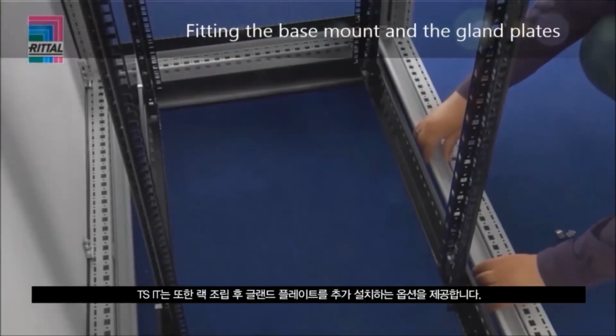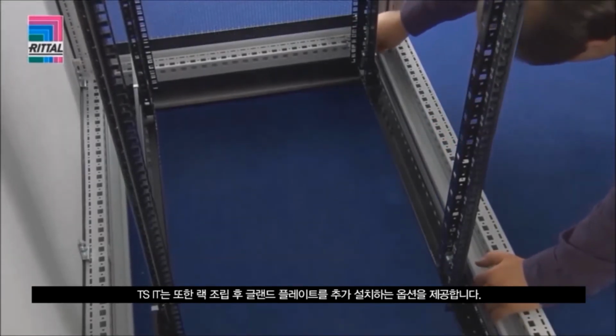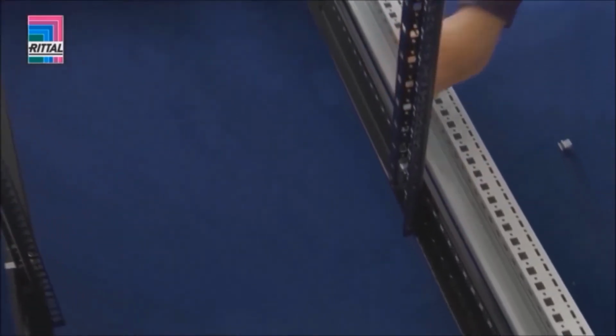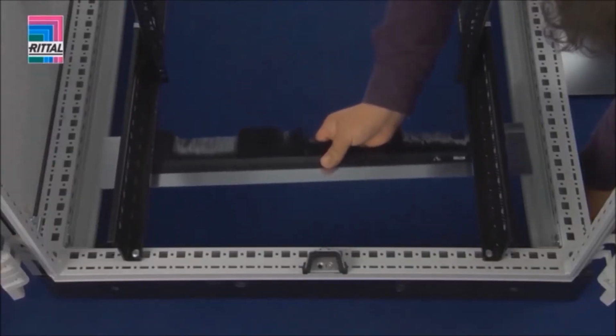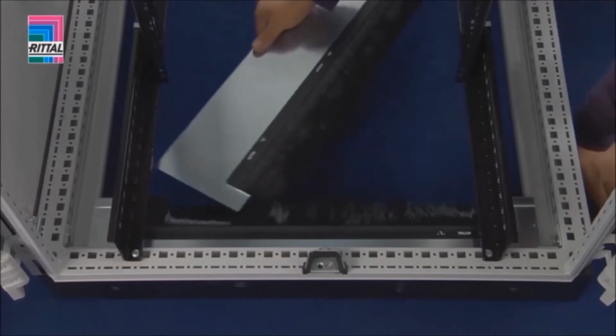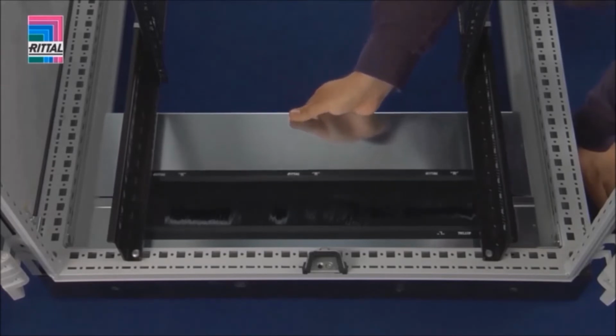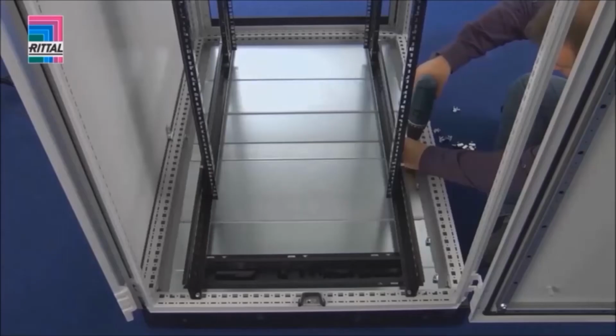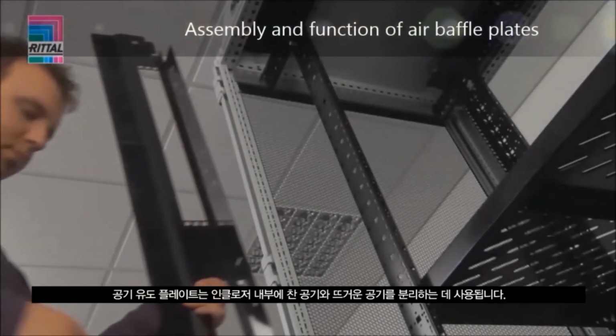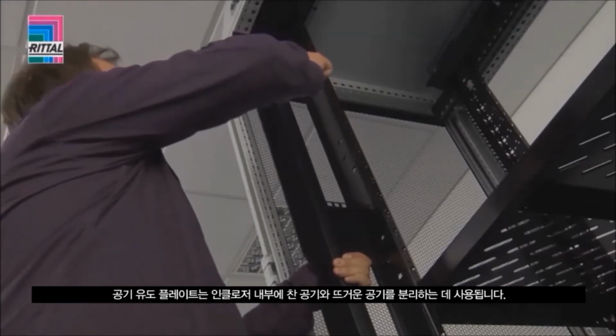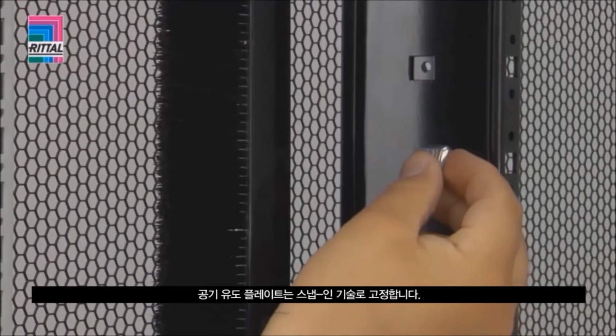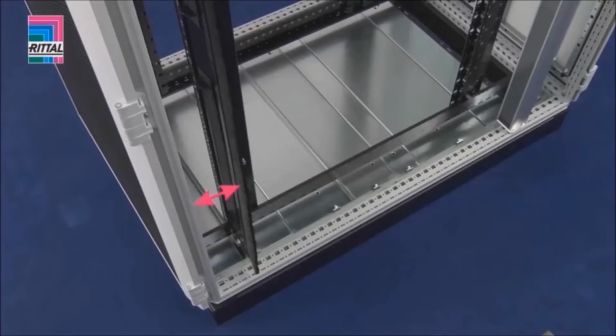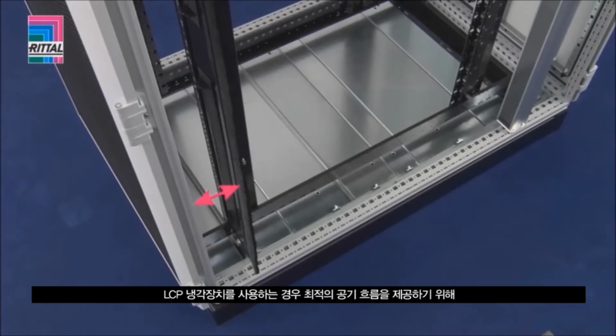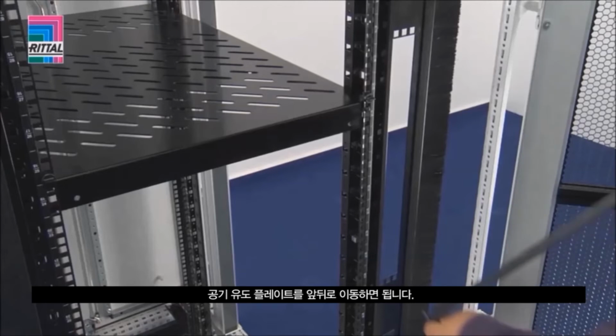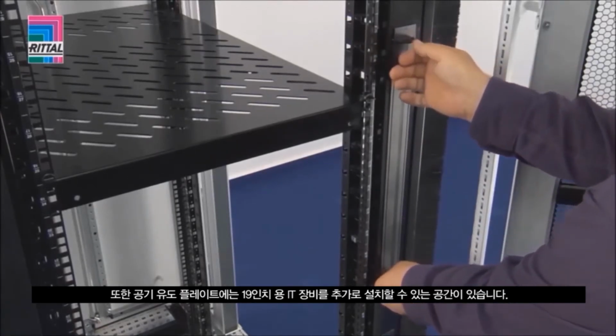The TSIT also offers the option of retrofitting gland plates after rack assembly. The air baffle plates are used to separate the cold and hot zones inside the enclosure. They are secured using snap-in technology. For optimal air routing when using an LCP, the air baffle plates are simply rotated. Additional vertical height units in the air baffle plates provide extra assembly space.